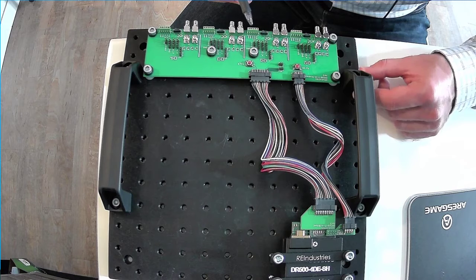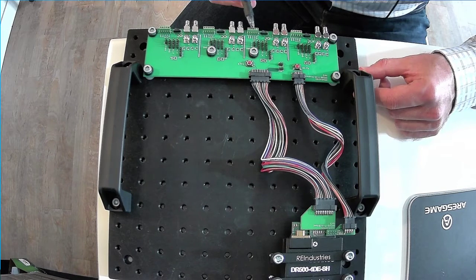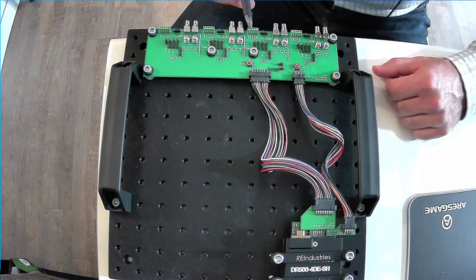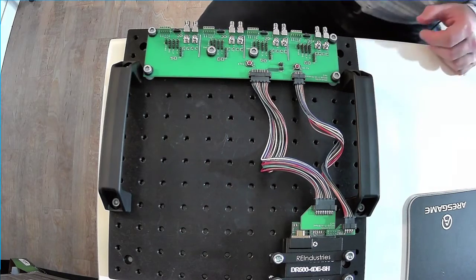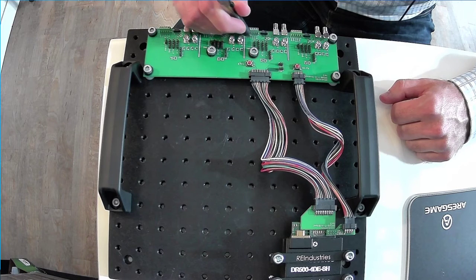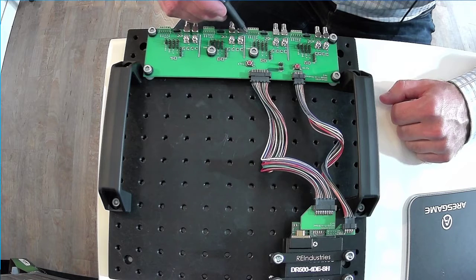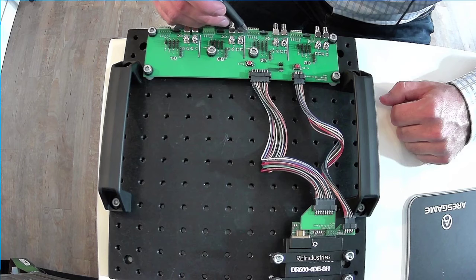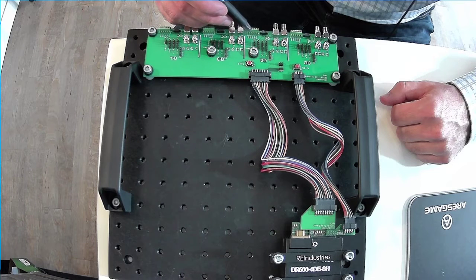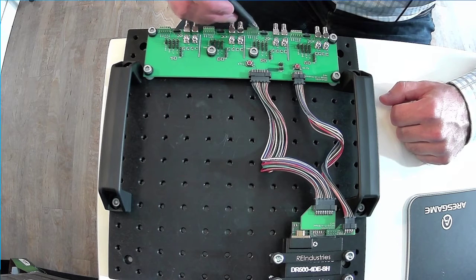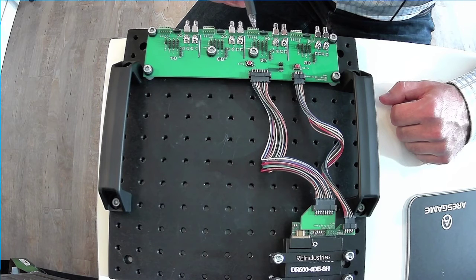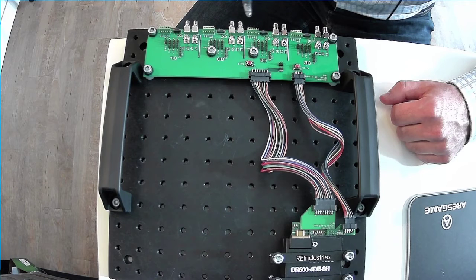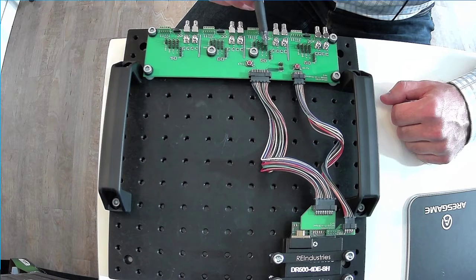And so the next interface point is a terminal block. This is just a standard terminal block. You can connect up anything manually and just screw it down. The terminals are labeled on the silkscreen. So this one has six pins, two grounds. One can be used for shield, a regular ground, the P and N for the differential sensor signals, and an excitation voltage or V bias. And so this is just a general input, but it can be used for all different accelerometers. So you have the freedom to manually connect up pretty much anything you want here. You also have the freedom to connect up anything that you want here as well.